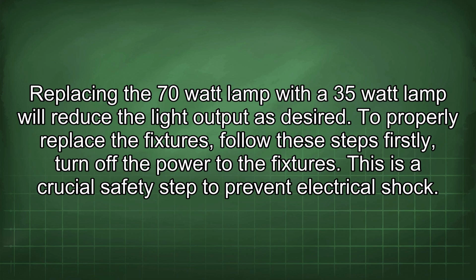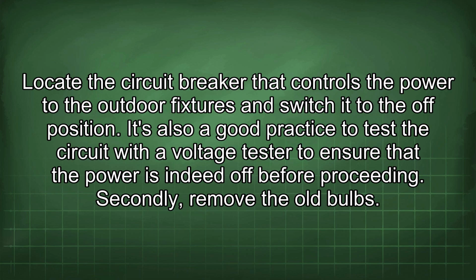To properly replace the fixtures, follow these steps. Firstly, turn off the power to the fixtures. This is a crucial safety step to prevent electrical shock. Locate the circuit breaker that controls the power to the outdoor fixtures and switch it to the off position.